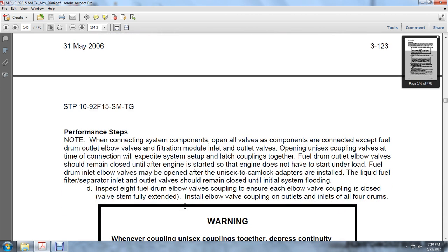When performing the steps, note: when connecting system components, open all the valves as components are connected, except the fuel drum outlet elbow valves and the filtration module inlet and outlet valves. Open the unisex coupling valves at the time of connection, which will expedite the system setup and latch couplings together. Fuel drum outlet elbow valves should remain closed until after the engine is started so that the engine does not have to start under load. Fuel drum inlet elbows may be opened after unisex cam lock adapters are installed. The liquid fuel filter separator inlet and outlet valves should remain closed until the initial system flooding.